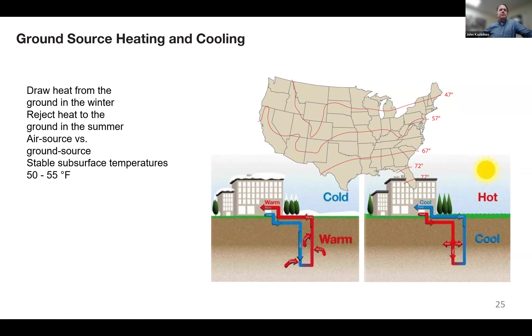So the geothermal system comprises a number of boreholes that are typically advanced with a water well drilling rig. These are open boreholes in rock. We install loop piping, which is typically high-density polyethylene piping. It's all closed with thermal welds, so we're not pumping any groundwater. We're not circulating any groundwater.